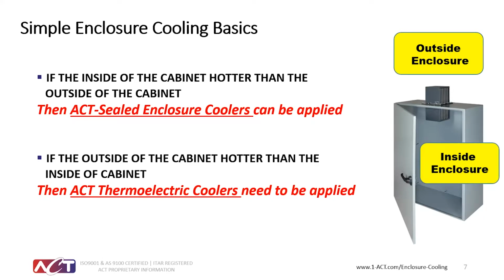ACT features two products for above ambient passive sealed enclosure cooling. They essentially differ in heat transfer technology, mounting size, orientation, panel depth, and heat load dissipation capacity. Depending upon the application, heat exchangers are a great choice over air conditioner enclosure cooling. They are cost-effective to operate and have minimal maintenance requirements.